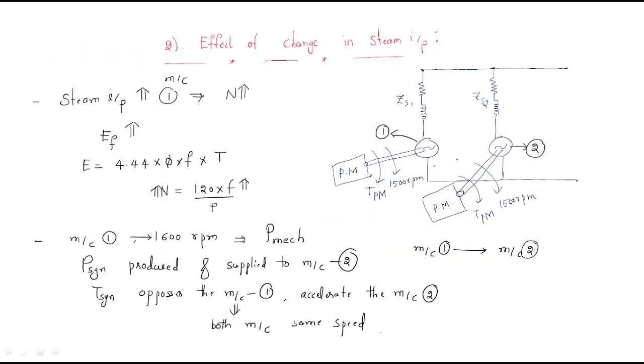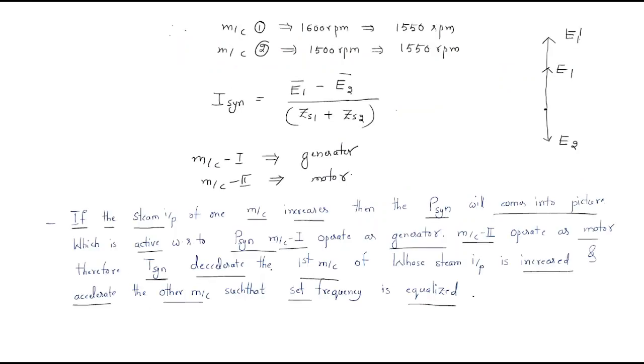To summarize: when two alternators are operated in parallel and one machine has more steam input, synchronizing power is generated and synchronizing torque is produced. That torque maintains constant speed for both machines. Machine one operates as a generator and machine two operates as a motor during this transient period.